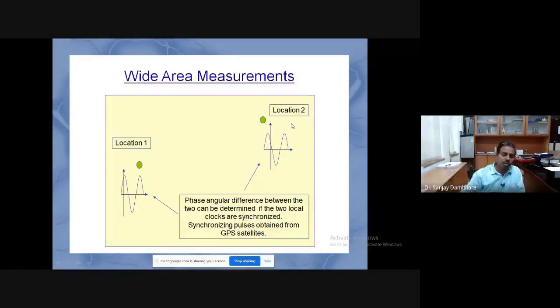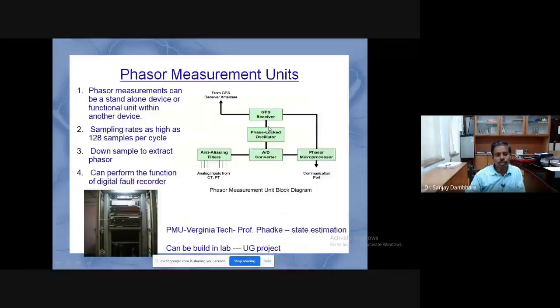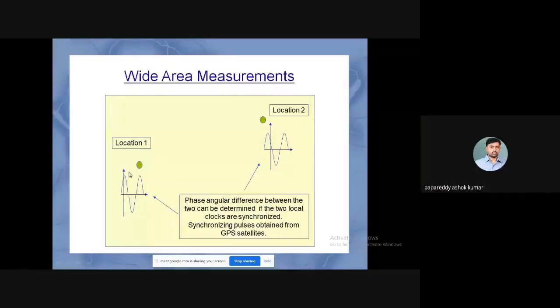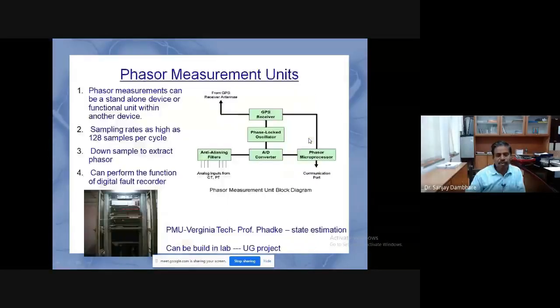Synchronizing pulses are obtained from the GPS, so the clock is the same, and then DSPs which compute the phasors are used — these are called PMUs. PMU stands for phasor measurement unit. The PMU takes the signal from CT and PT, and the time signal from the GPS, and the microprocessor or DSP hardware computes the phasor value, which is then made available on the communication port.